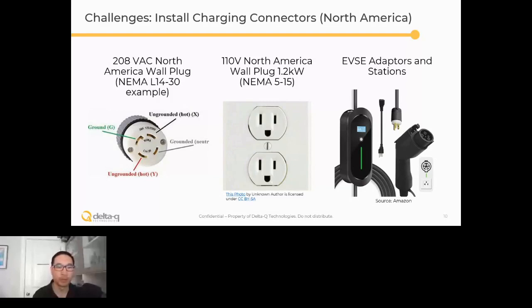So the 14-30, the 30 means 30 amps. You can pull 24 amps continuously out of it based on the National Electrical Code's 80% guidance. So you're really looking at like 5 or 6 kilowatts of charging out of what you might most commonly find on a construction site.